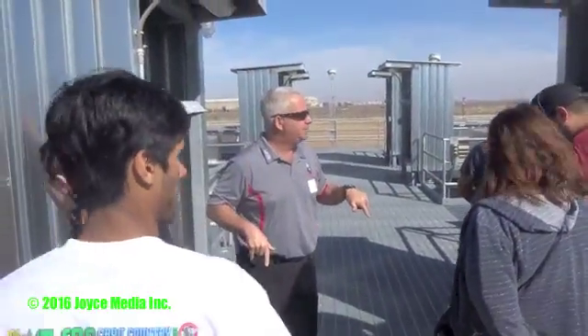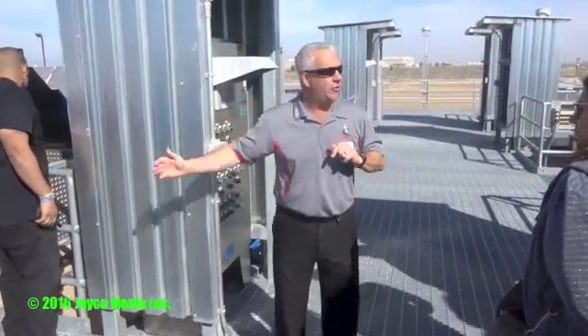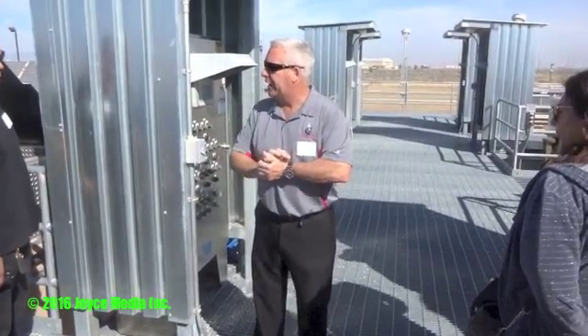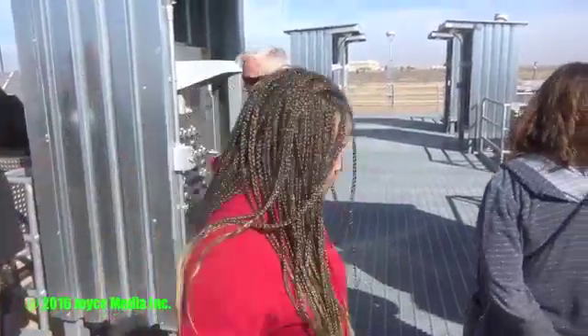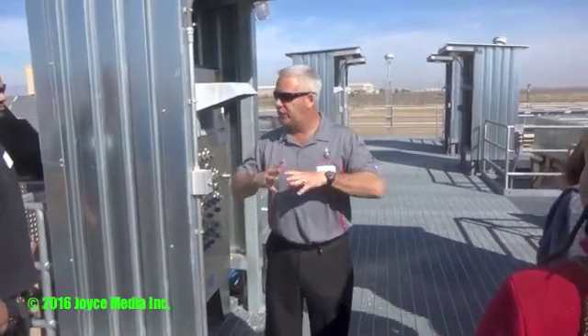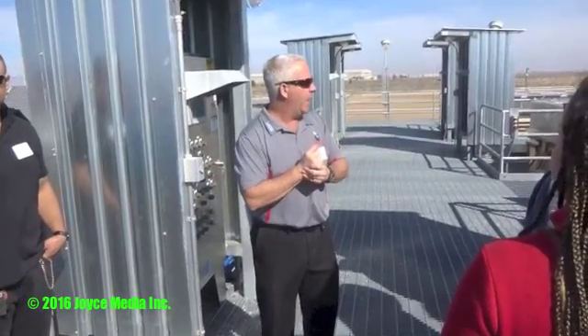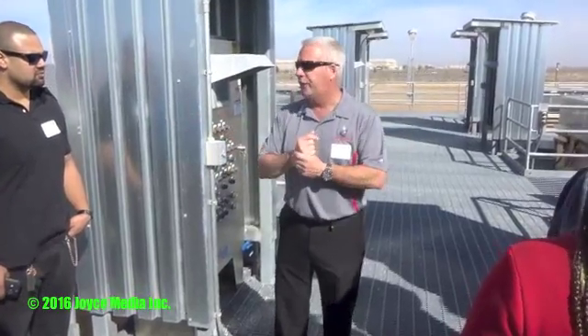What is happening is we put the secondary effluent from the clarifiers into these filters at a specific level. That pressure of the water forces the water through the filter and it comes out and goes off toward the chlorine contact tank. These filters are cleaned about every 24 hours. They just have water run through them backwards. Take clean water, run it through backwards, and that water goes out to the basin where it's another attempt. You can see how clean the water is through the filters.